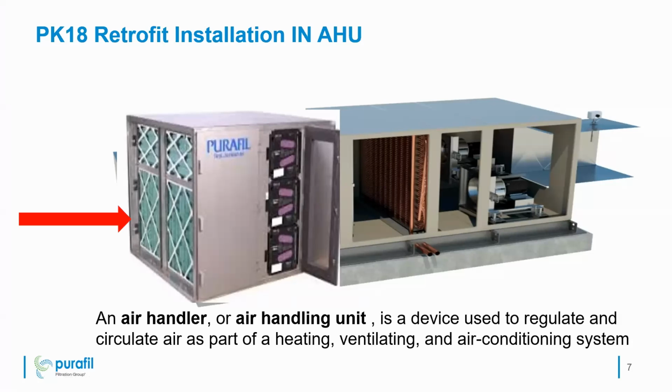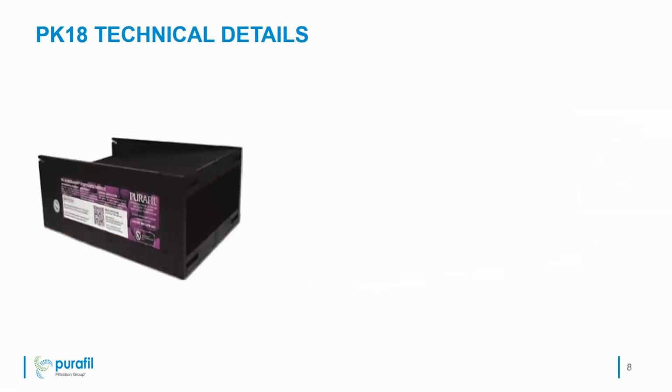So this is a module which you have to install in the existing HVAC system. So you should know what the dimension is, how to select, what details we need to collect from the site, what the pressure drop is, because that is going to be taken care of by the AHU, whether it is capable. Do we need to change the motor? Do we need to increase the VFD speed? Do we have to change the pulley? So these are the details.